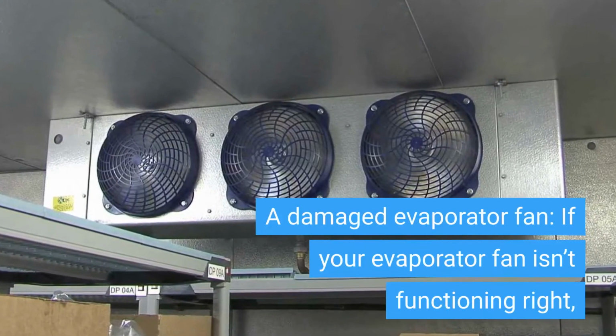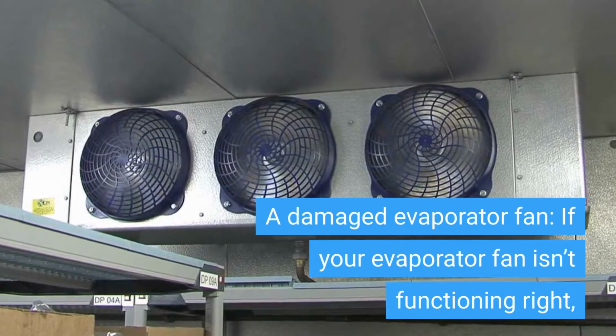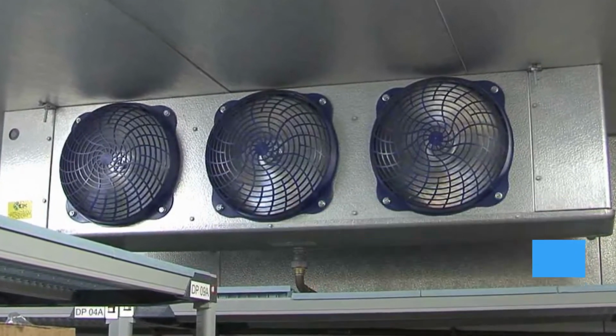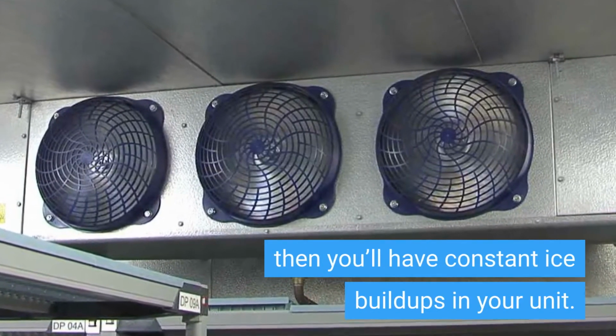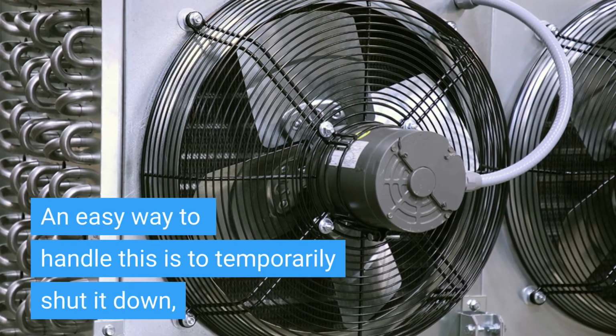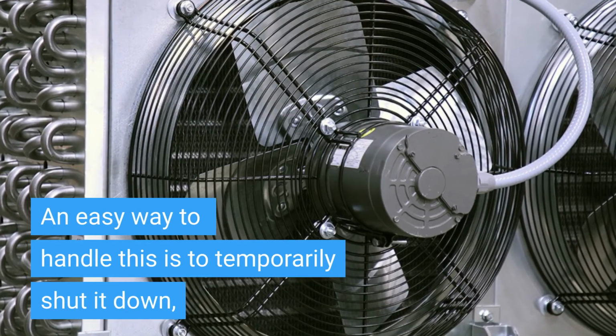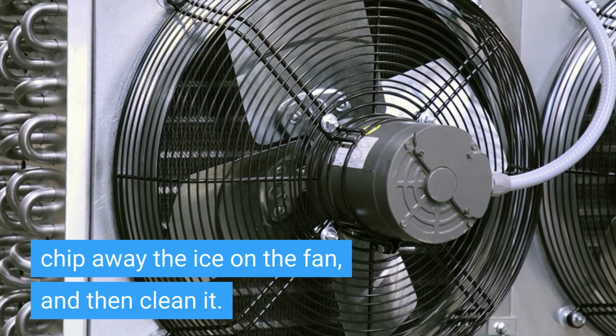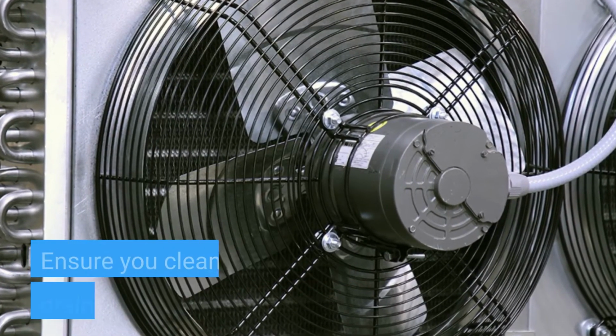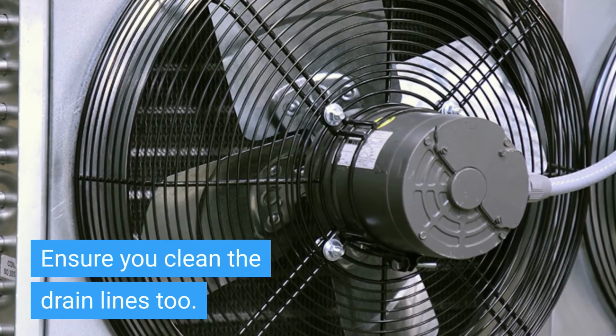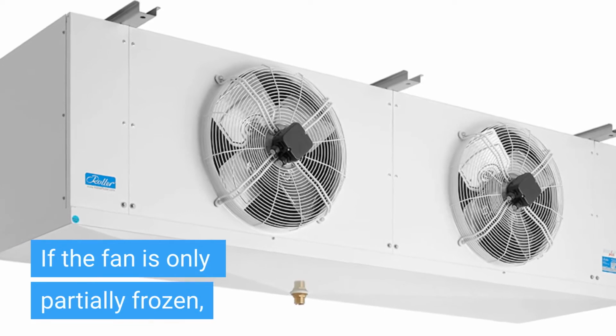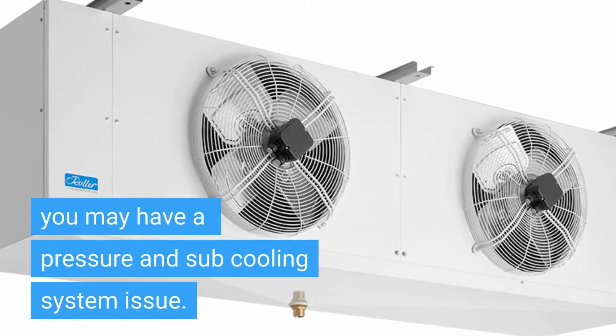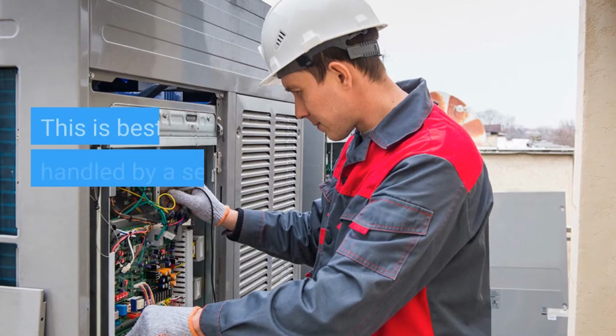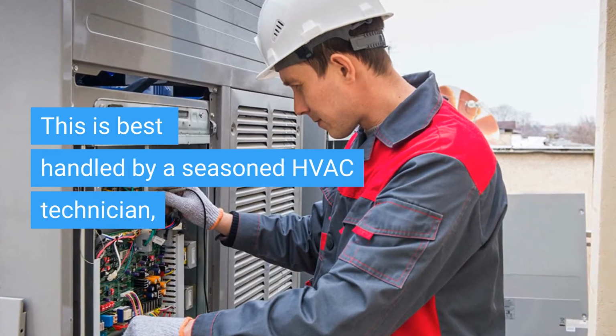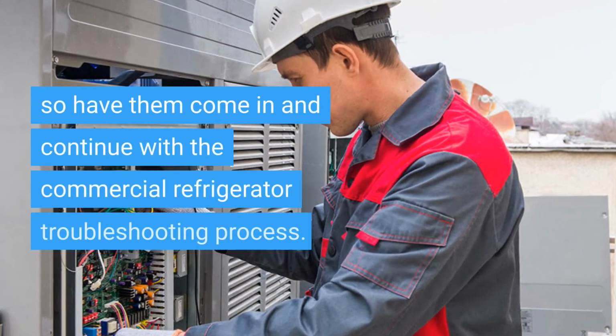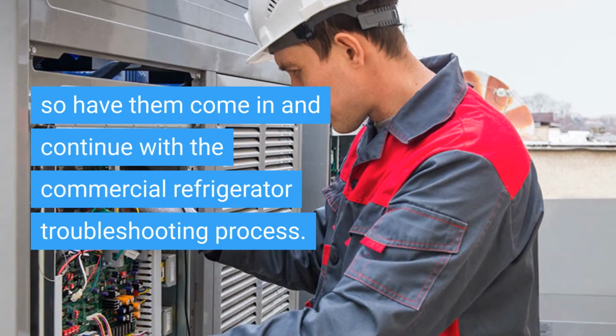A damaged evaporator fan. If your evaporator fan isn't functioning right, then you'll have constant ice buildups in your unit. An easy way to handle this is to temporarily shut it down, chip away the ice on the fan, and then clean it. Ensure you clean the drain lines too. If the fan is only partially frozen, you may have a pressure and subcooling system issue. This is best handled by a seasoned HVAC technician, so have them come in and continue with the commercial refrigerator troubleshooting process.